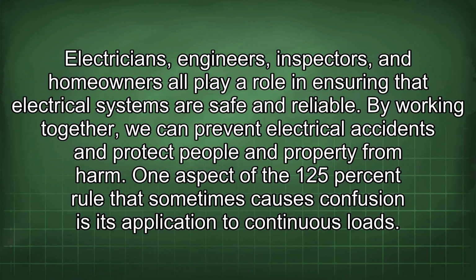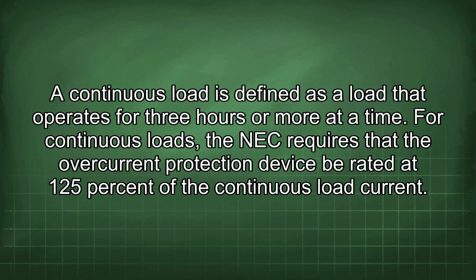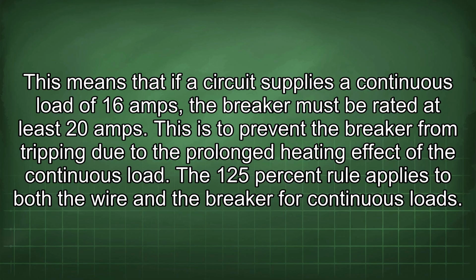One aspect of the 125% rule that sometimes causes confusion is its application to continuous loads. A continuous load is defined as a load that operates for 3 hours or more at a time. For continuous loads, the NEC requires that the overcurrent protection device be rated at 125% of the continuous load current. This means that if a circuit supplies a continuous load of 16 amps, the breaker must be rated at least 20 amps. This is to prevent the breaker from tripping due to the prolonged heating effect of the continuous load.